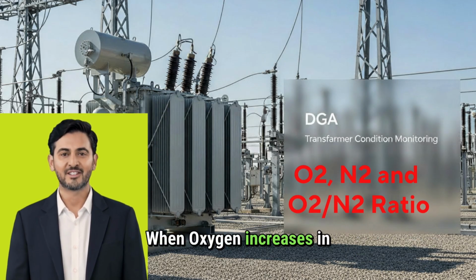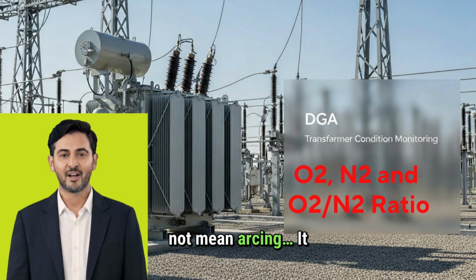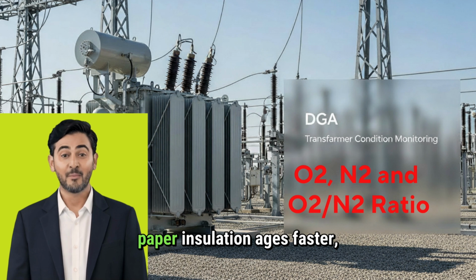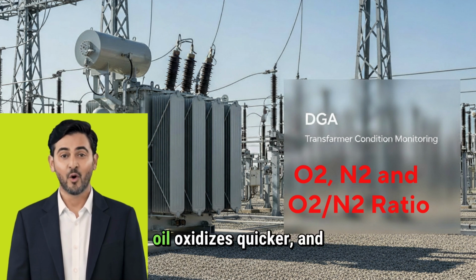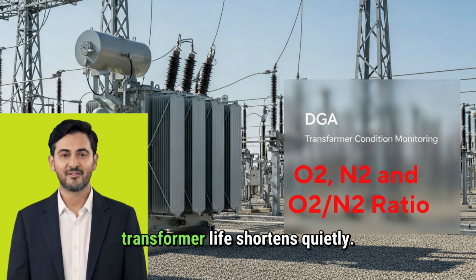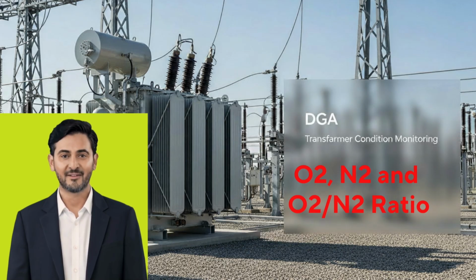When oxygen increases in DGA, it does not mean overheating. It does not mean arcing. It means something far more silent. Air is entering the transformer. And when oxygen enters, paper insulation ages faster, oil oxidizes quicker, and transformer life shortens quietly.